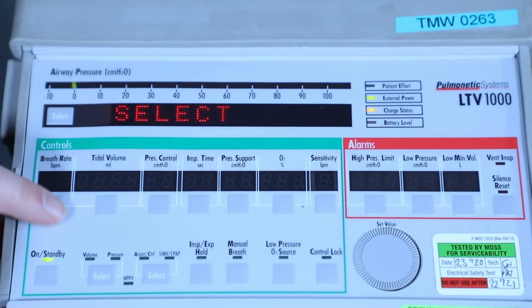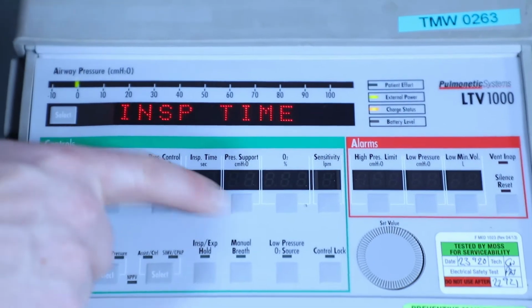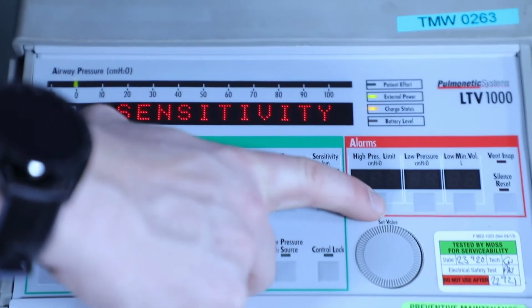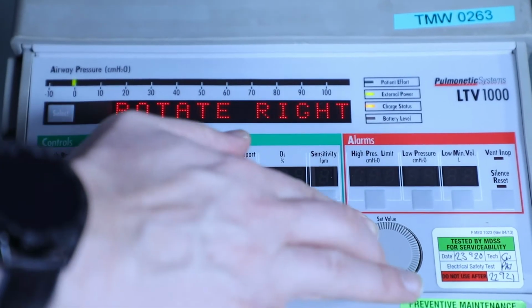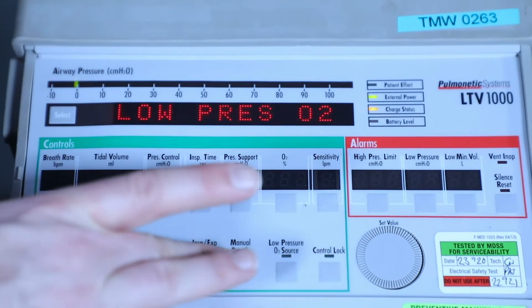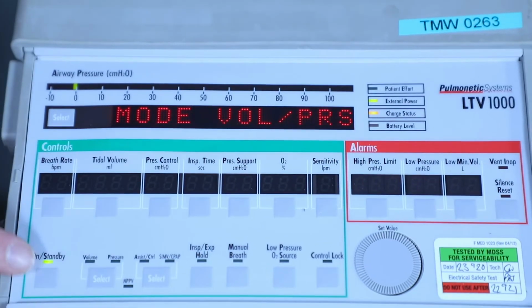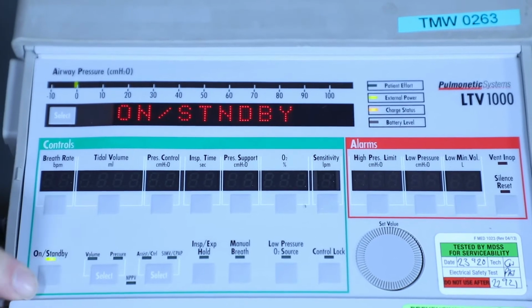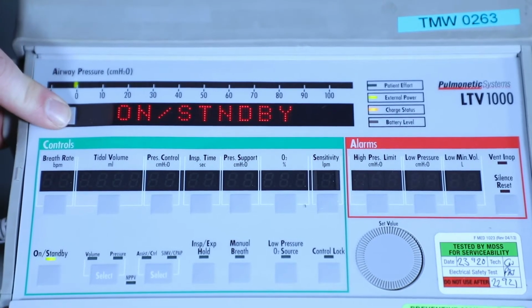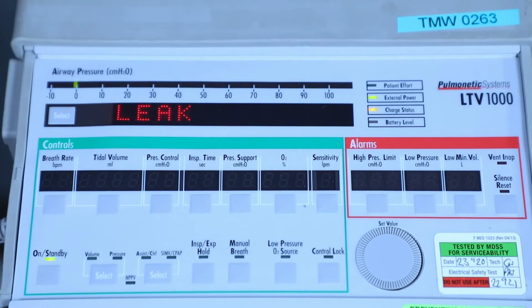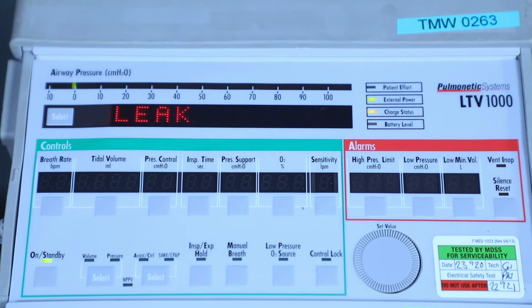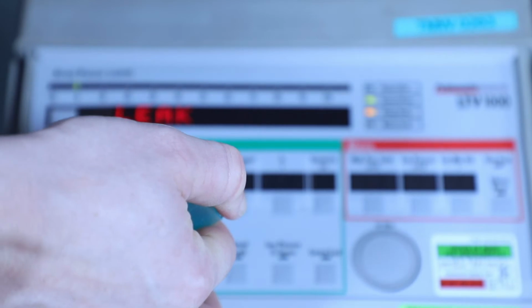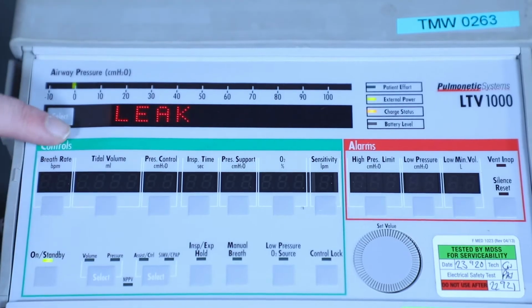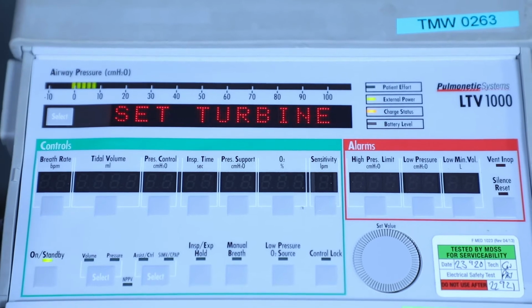Starting with the select button, we move through each of the buttons, ensuring what is displayed is accurate to its description. Remember to include the on-off button to test for this. Then we can press the select to test for the pressure and the leak in the system. We must occlude the system, the circuit, using our thumb. We can then press select for the leak test to run.